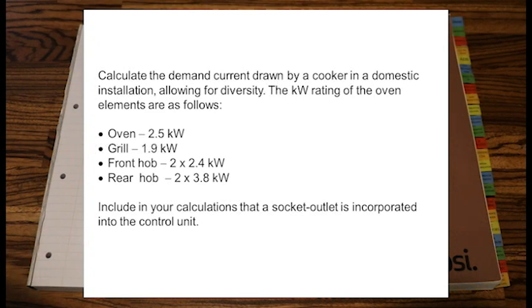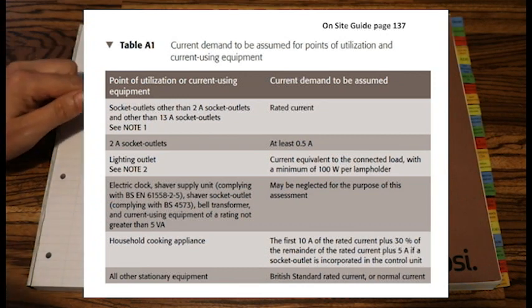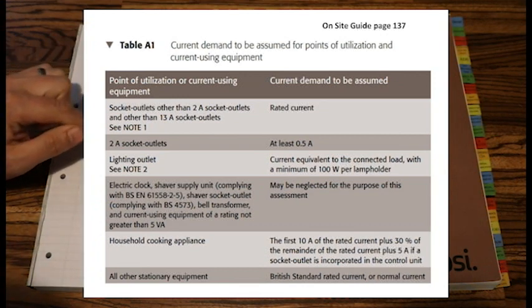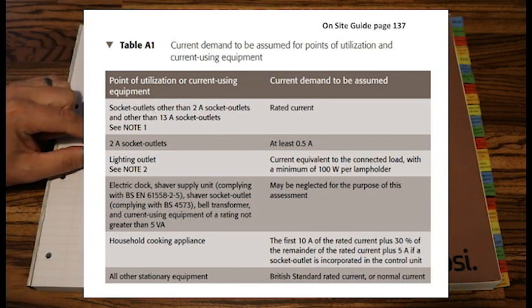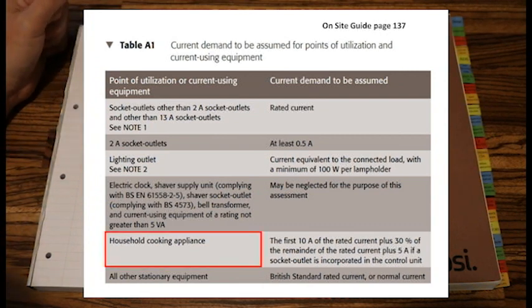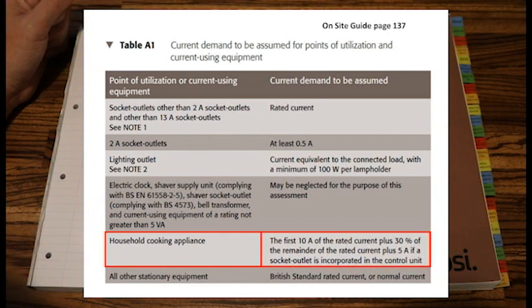So Table A1, if we look down, one, two, three, four, five. So fifth one down, it says household cooking appliance. And then on the second column, it says the first 10 amps of the rated current plus 30% of the rated current plus 5 amps if a socket outlet is incorporated into the control unit.